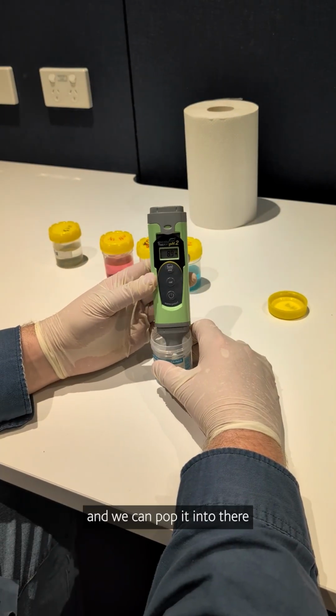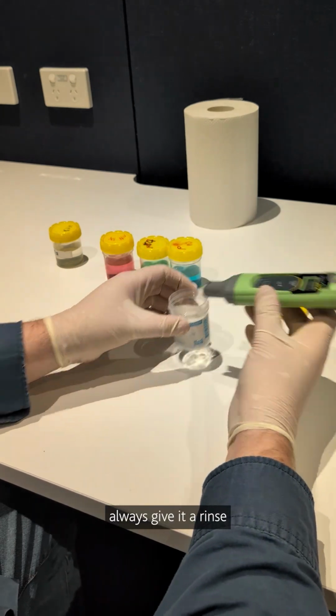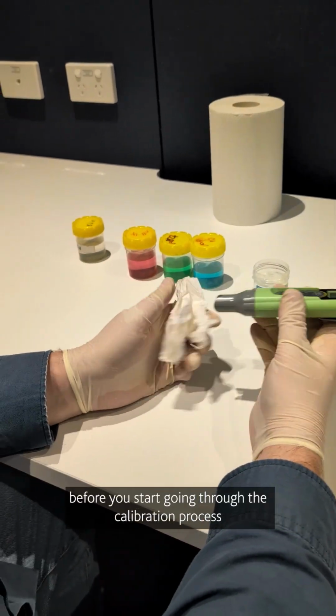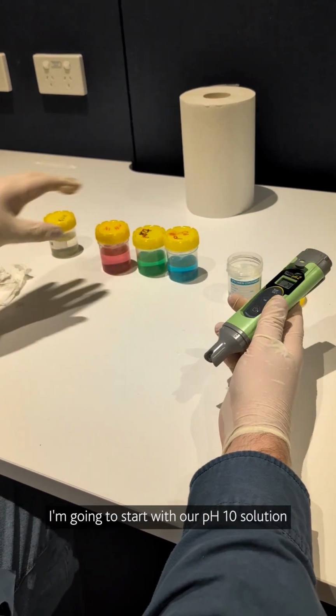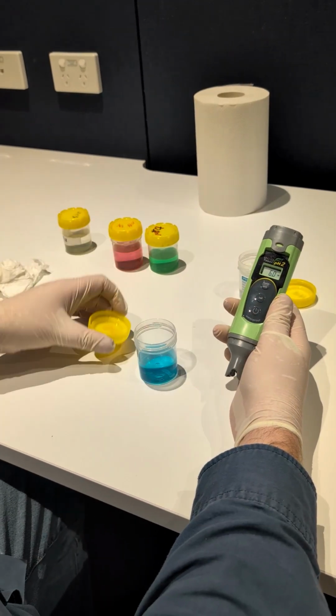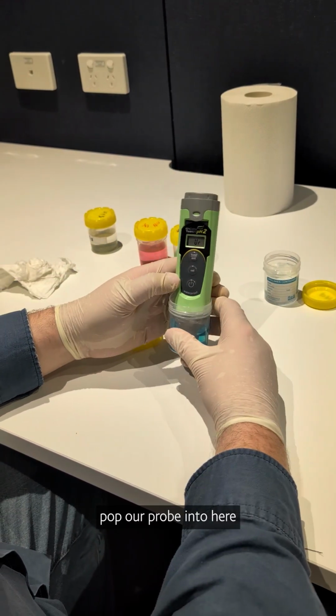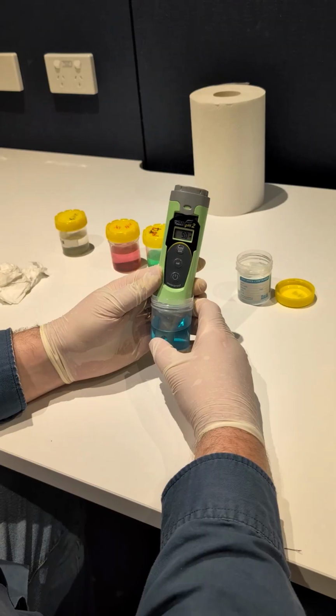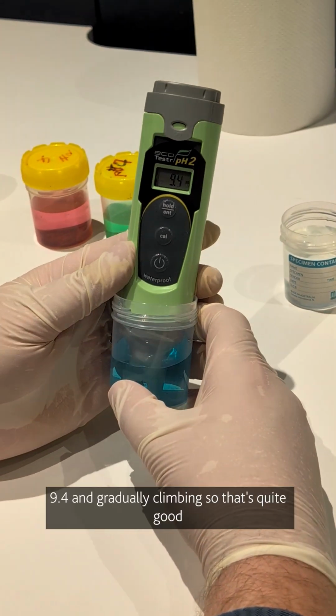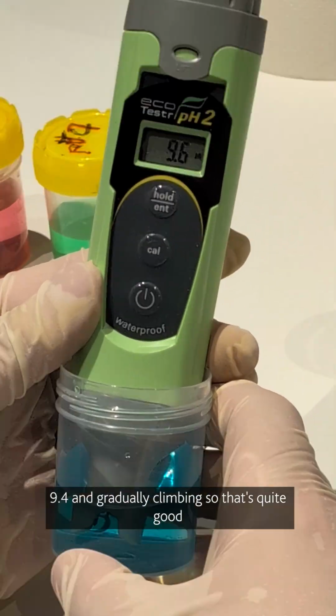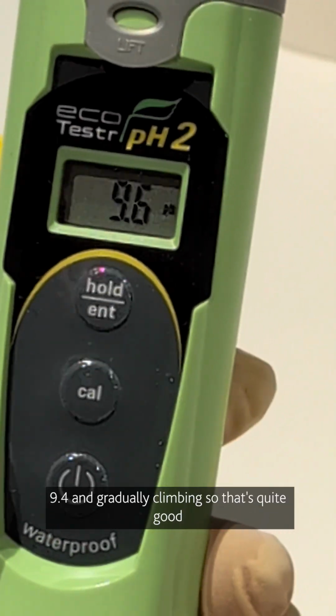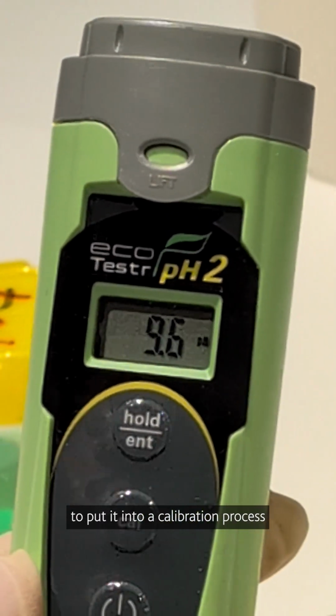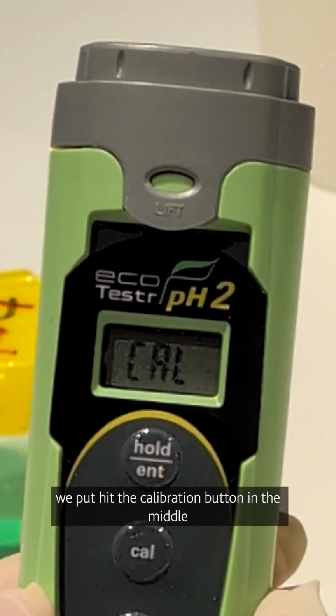We can pop it into there. Always give it a rinse before we start going through our calibration process. I'm going to start with our pH 10 solution. So we'll pop our probe into here. And that's reading about a 9.3, 9.4, and gradually climbing. So that's quite good. To put it into a calibration process, we hit the calibration button in the middle.